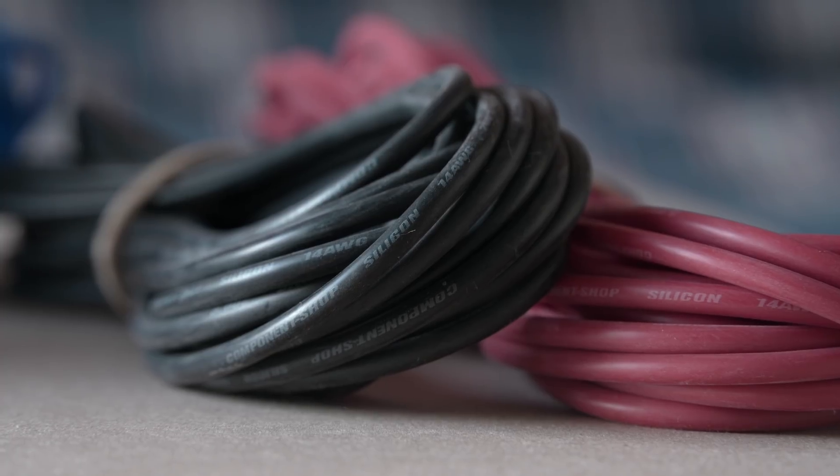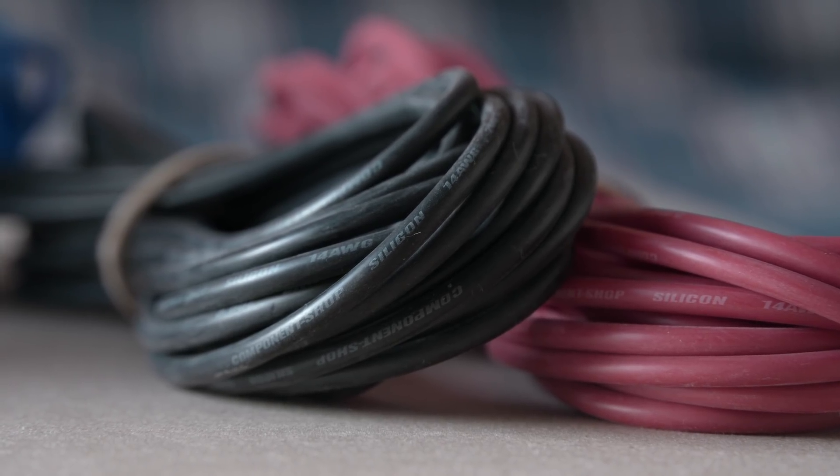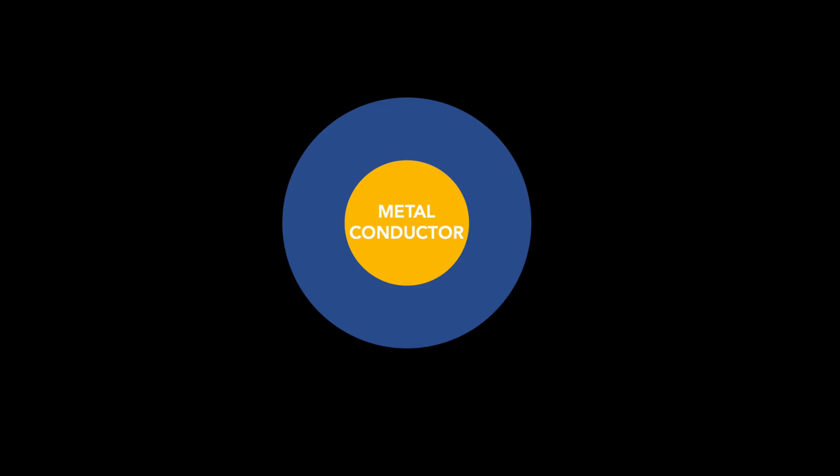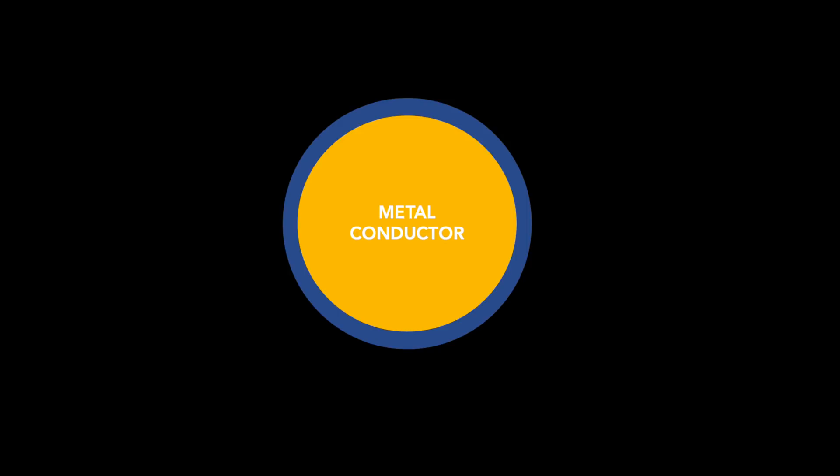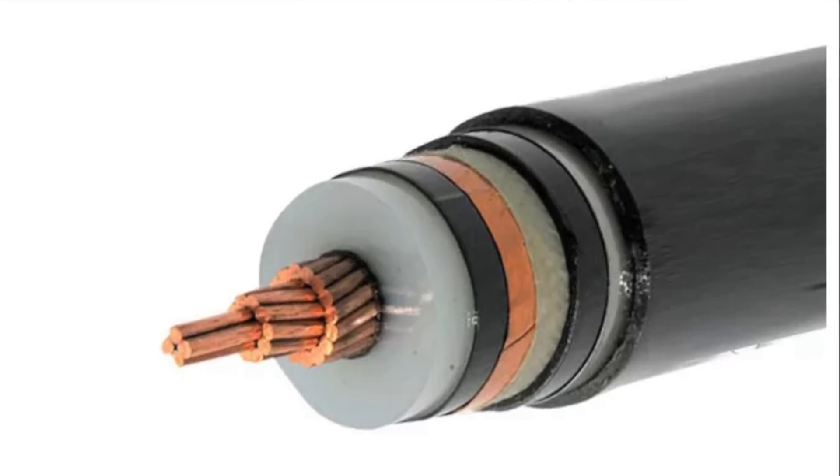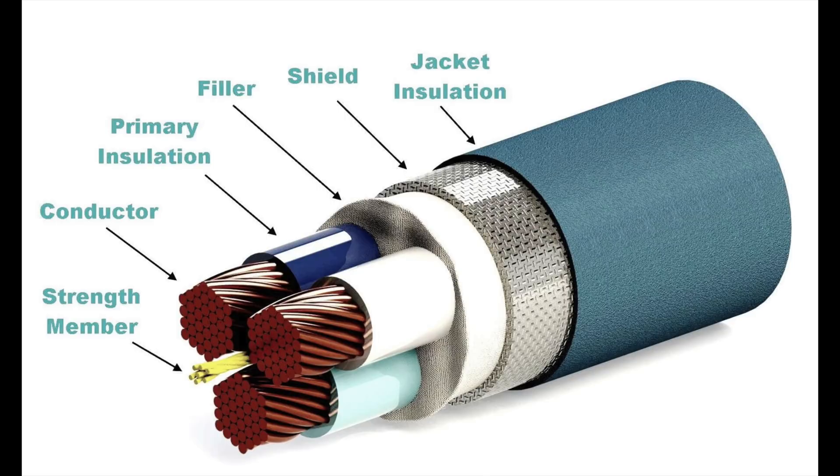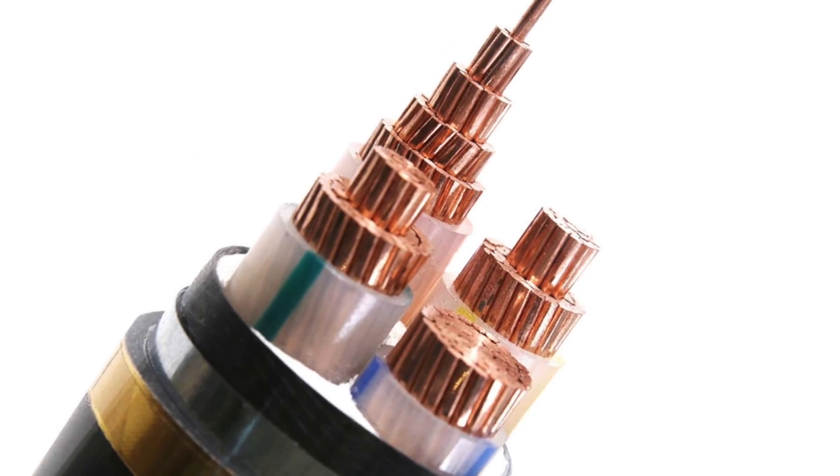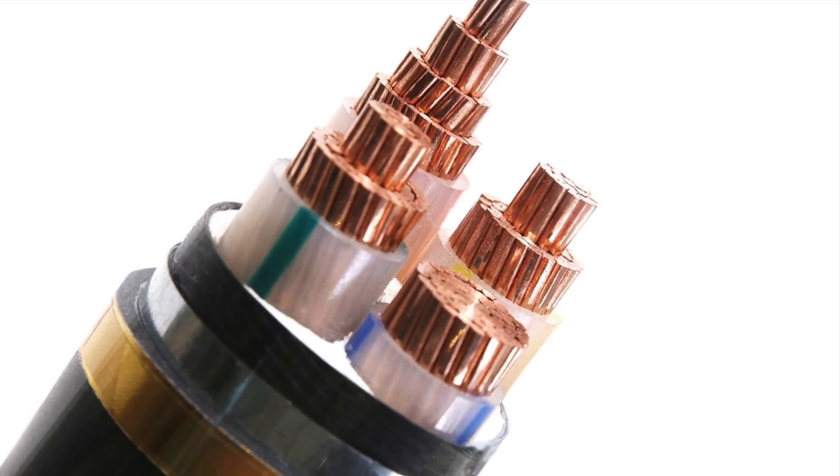Something else to keep in mind when deciding on your wiring, the physical sizes, and the capacity of your conduits, and so on. The thickness of the wire, or the cable if you have two or three conductors bundled together, isn't necessarily indicative of the amount of conductor in there. Wire sheaths vary, from single skin to multi-jacketed ones, reinforcements, and so on. A seriously chunky cable might be as tough as hell, but still not actually have as much conductive metal inside as you expect. So, check the specifications, or cut the wire and measure it.